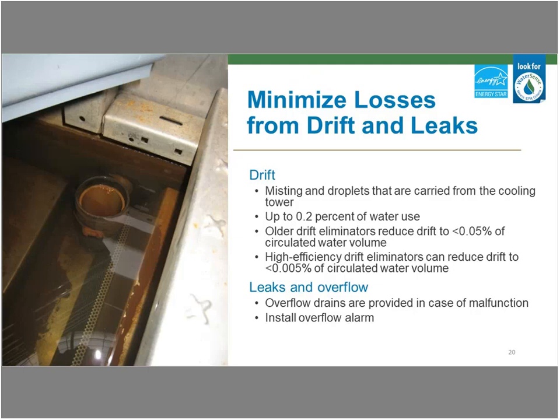So beyond the water evaporated, some water can be lost due to drift or splash out. In a well-designed tower equipped with drift eliminators, this should be relatively minimal. However, if you're noticing visible droplets exiting your tower or ponding near your tower, this may require some attention in your facility. If necessary, drift eliminators can be added to existing towers, or higher efficiency drift eliminators can be installed to replace older, poor-performing ones. High efficiency drift eliminators also have ancillary benefits, such as helping to reduce the risk of Legionella.